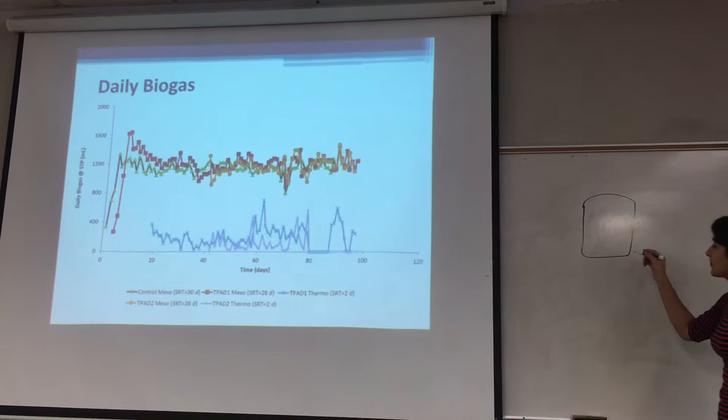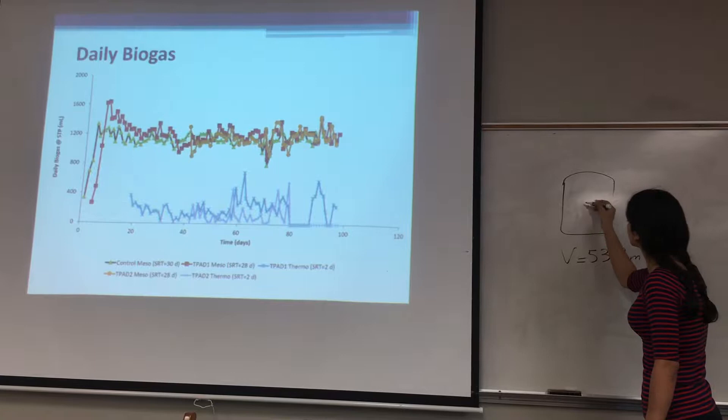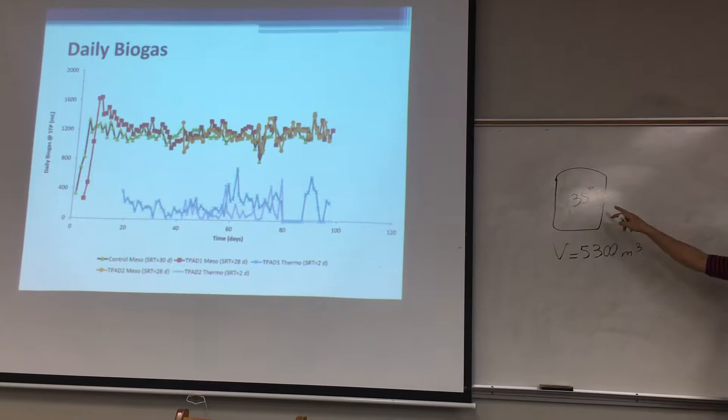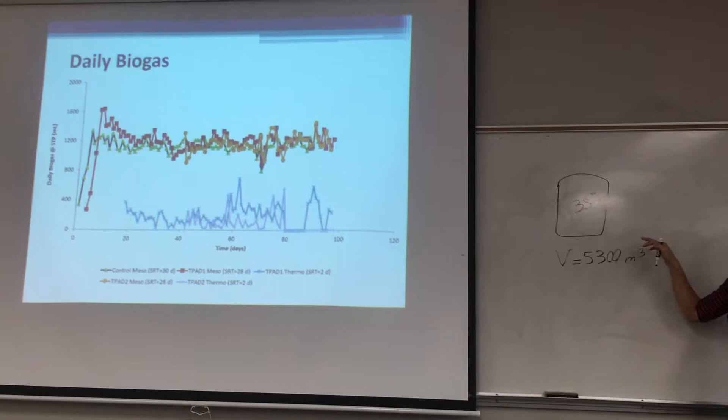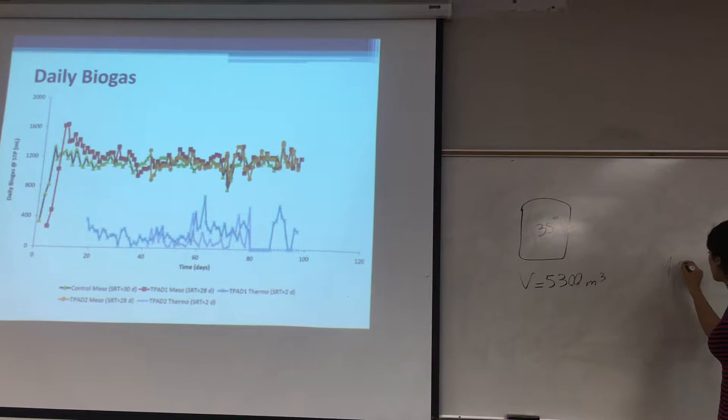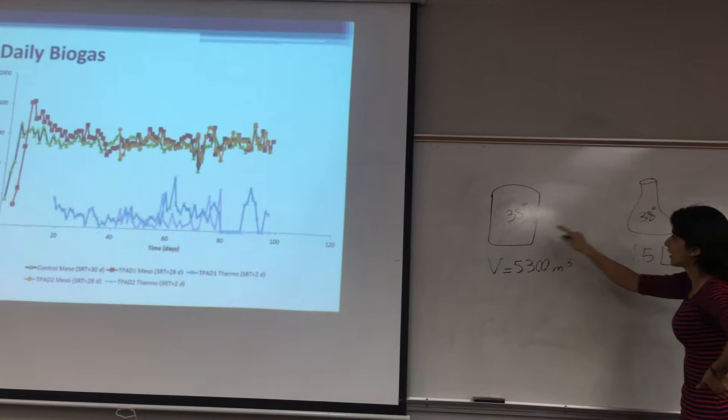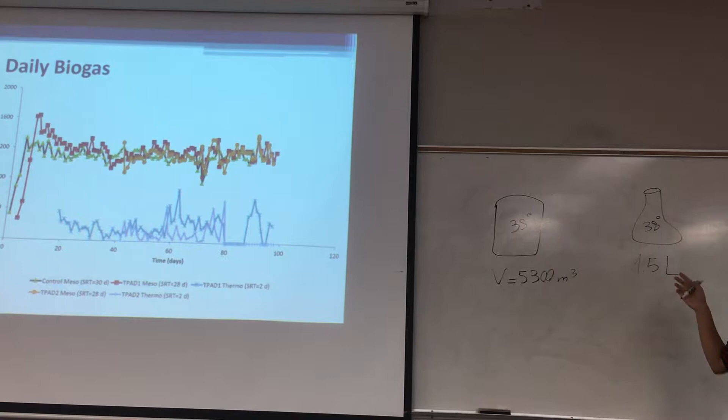Currently in Lulu Island they have a single stage anaerobic digester. The current volume is 5300 cubic meters, and the temperature is 38 degrees. So we are trying to make a similar one as our control digester. We have a 2 liter flask as a digester with a volume of 1.5 liters. We use the same temperature, 38 degrees, and the SRT is 31 days at Lulu Island, so we are using 30 days as our SRT.